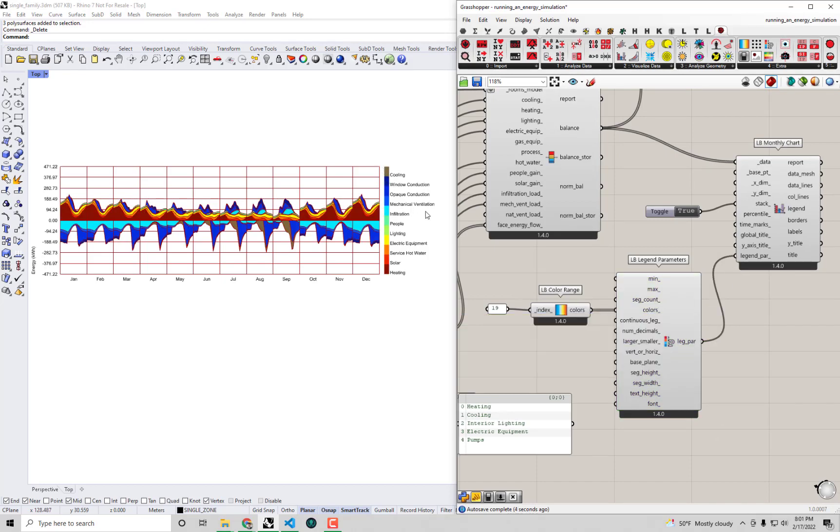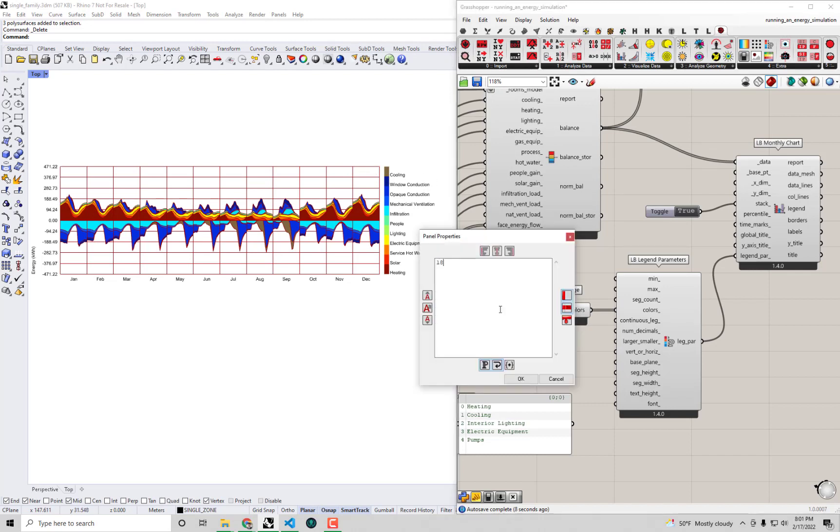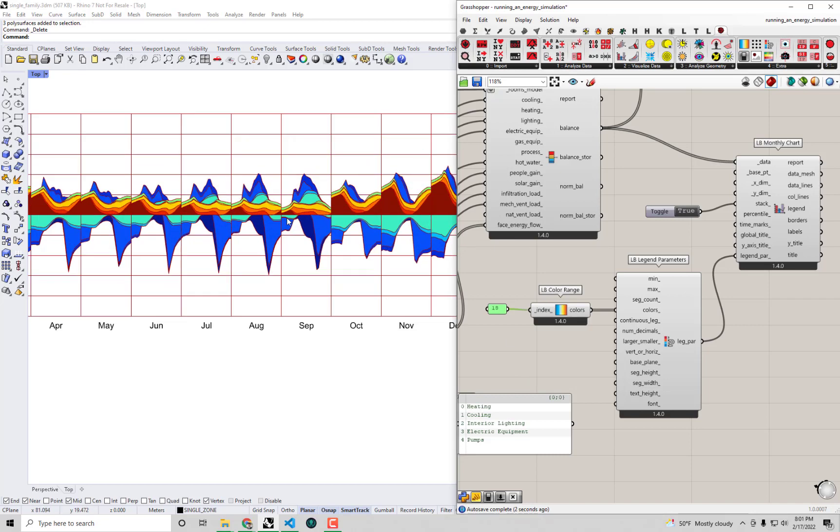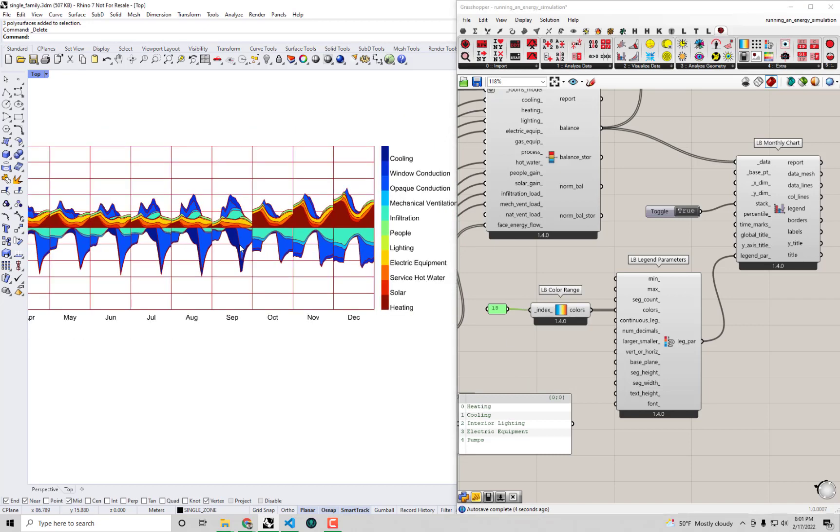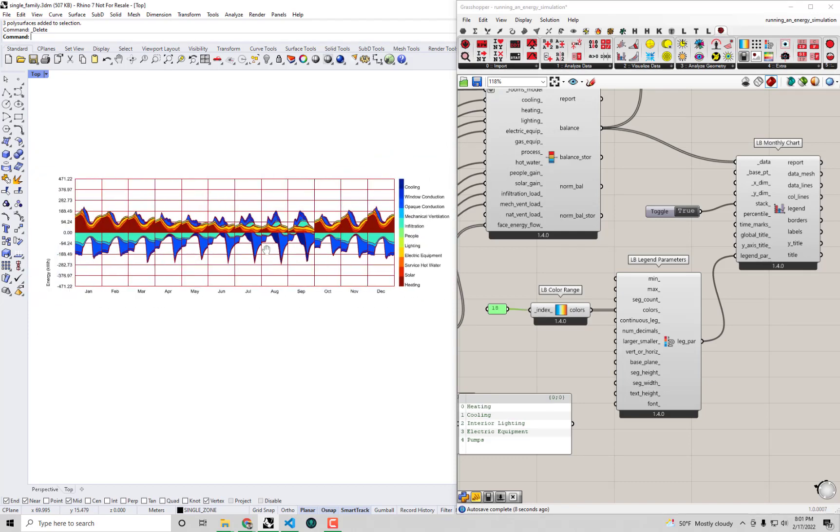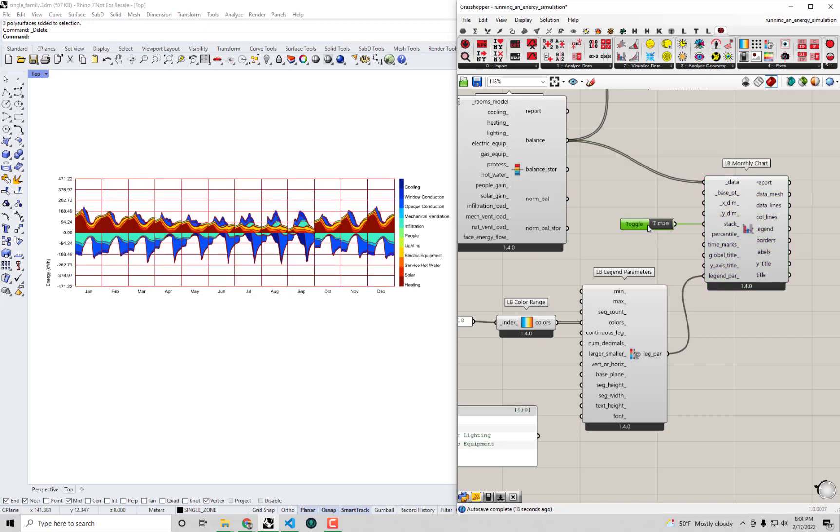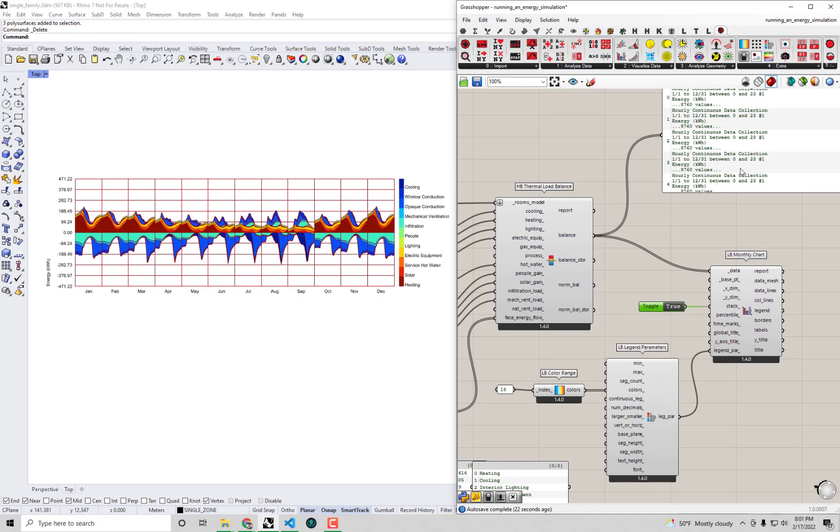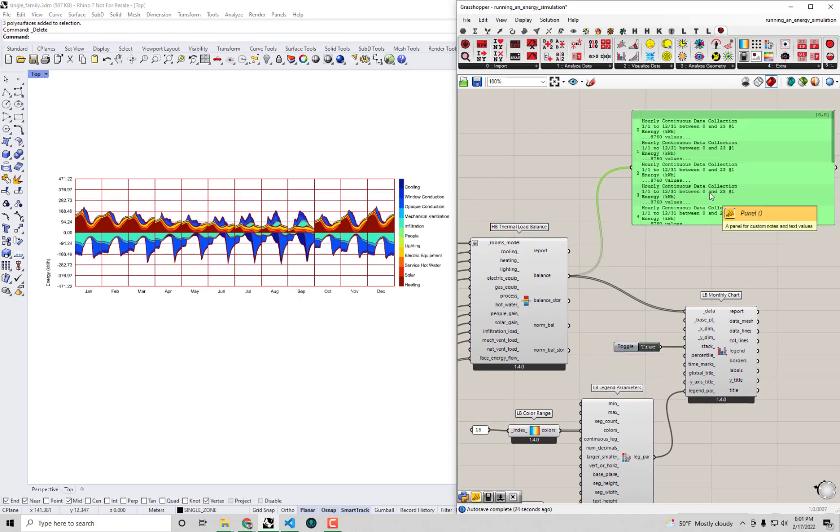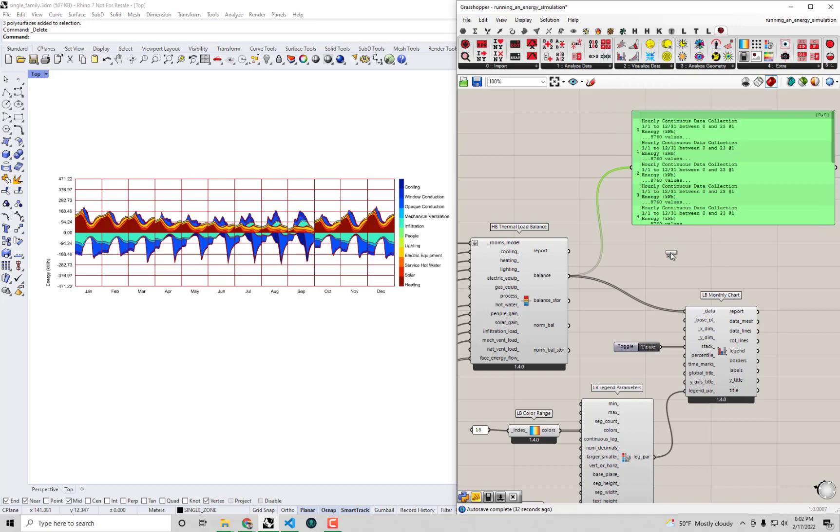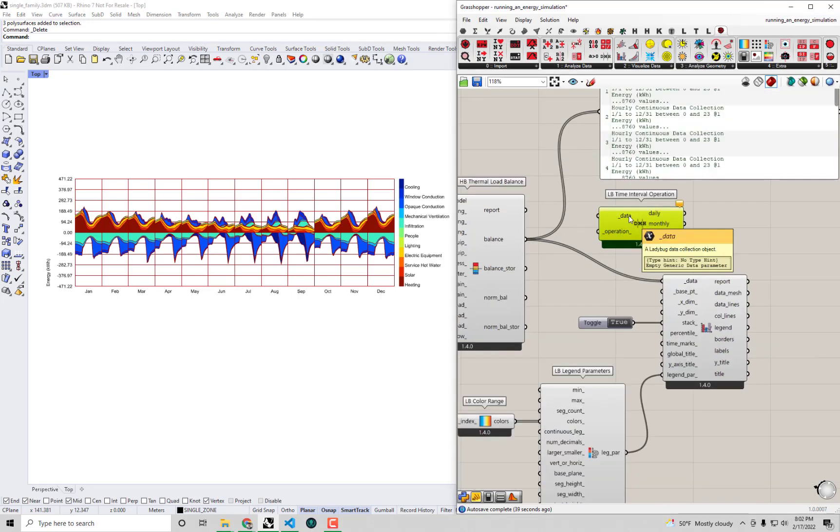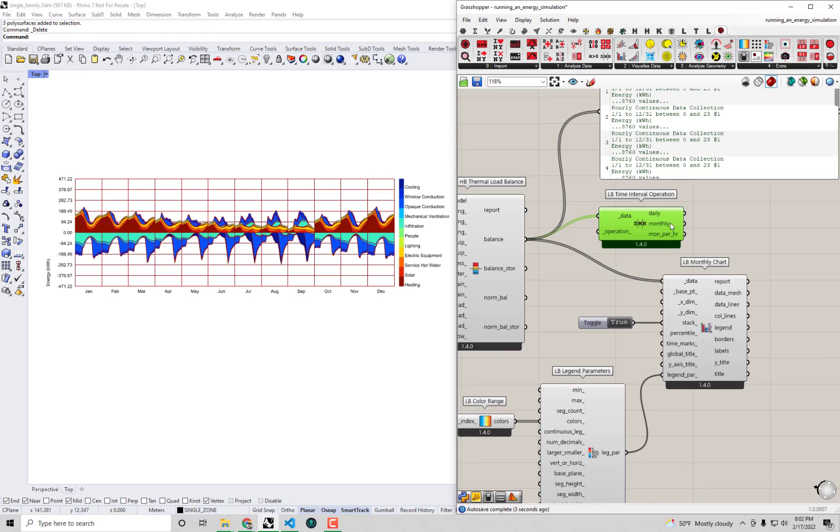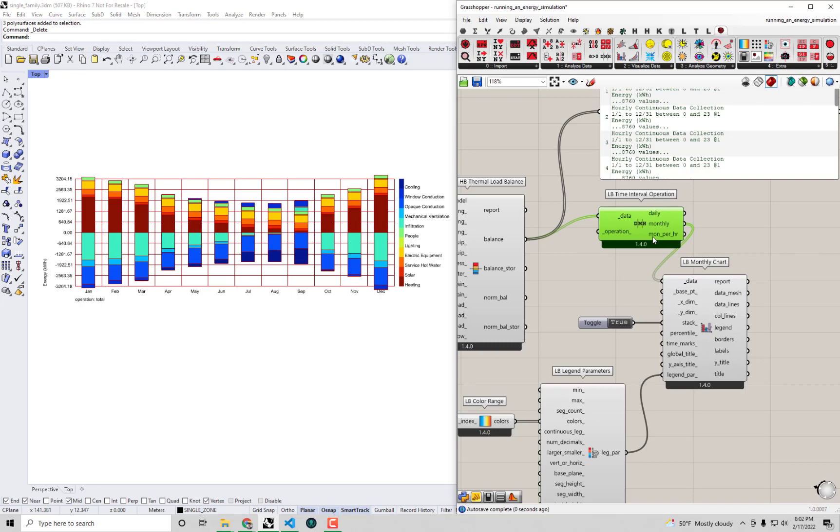And we should see this looks a little better. You can see the little brown color is maybe not exactly what we wanted for cooling. Maybe I can change this to 18 so that we can get a visualization that actually has dark blue for cooling. But in general, we can get a sense of what's really going on with the load balance over the course of this building. Honestly, though, this is not quite as clear as if we just had a nice monthly bar chart like in those other screenshots I showed you earlier. So in order to do that, what we can simply do is take these hourly data collections and convert them into monthly data collections. And there's an easy component that allows you to do this. It's just called LB time interval operation. And if you drop this onto the canvas, it allows you to take a data stream of hourly data and get it on either a daily, a monthly, or a monthly per hour basis. So the monthly is probably the key one that we'd like here. If I connect up our balanced data to our data of our time interval operation, and then I connect up the monthly data to our bar chart here, yeah, this is looking a lot more intuitive.